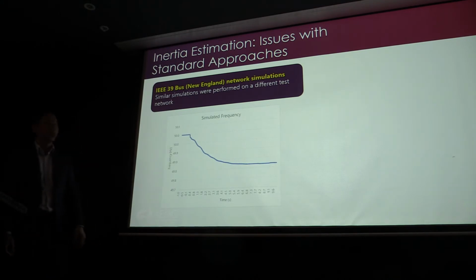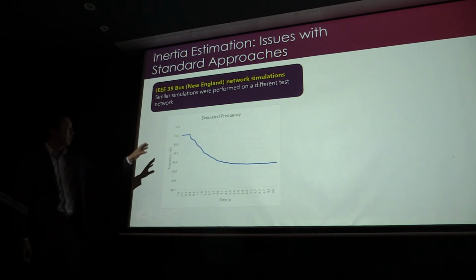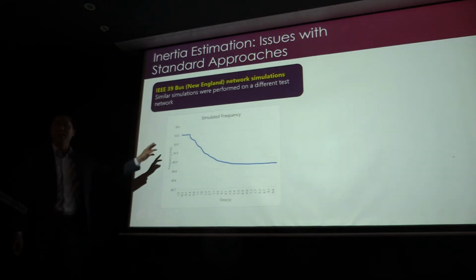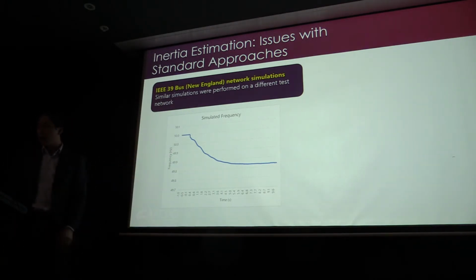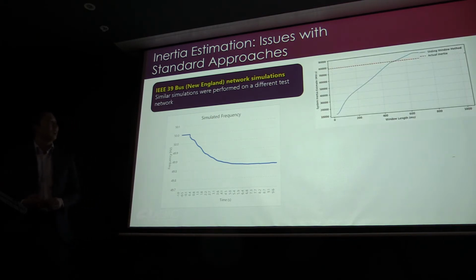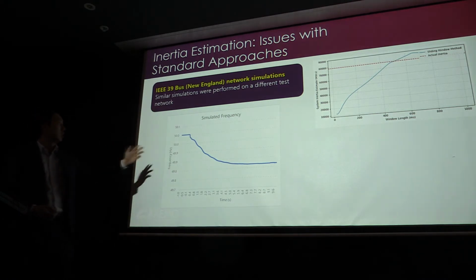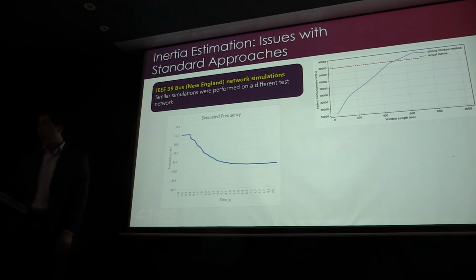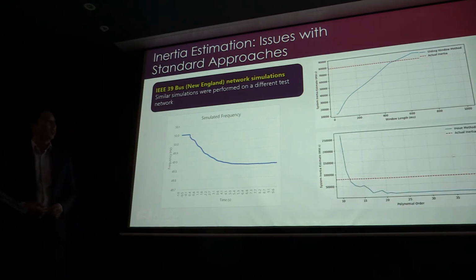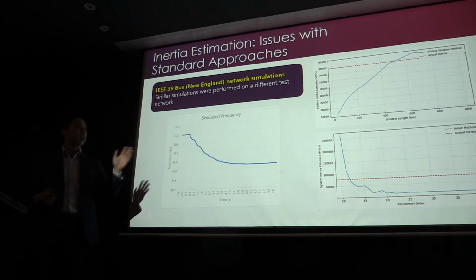And here is the frequency trace after a contingency. You can see that in this case there are some oscillations. This is one of the interesting things we wanted to highlight: all of a sudden 500 milliseconds doesn't look so bad anymore with the sliding window technique. In fact, if you go too low, it doesn't work because now you're picking up these oscillations. On the other hand, using the polynomial fit, it gets very bad because now you're overfitting all these oscillations. So there are some material problems with trying to use these methods when you have different configurations in your network and different contingency types.